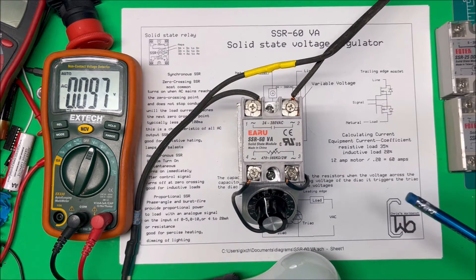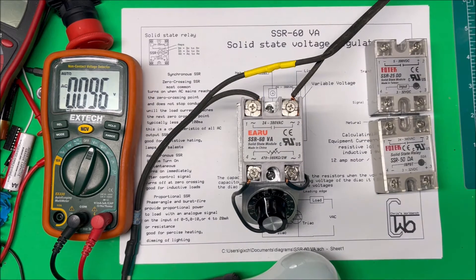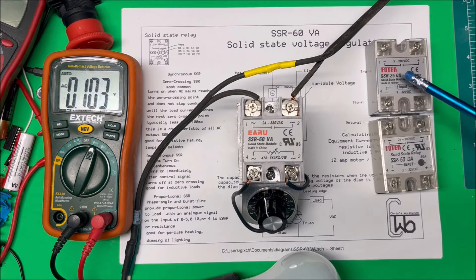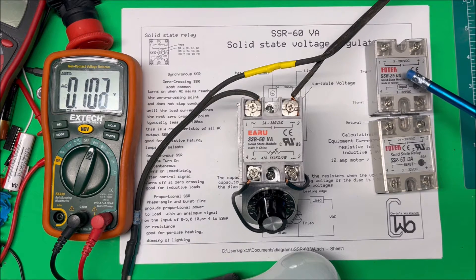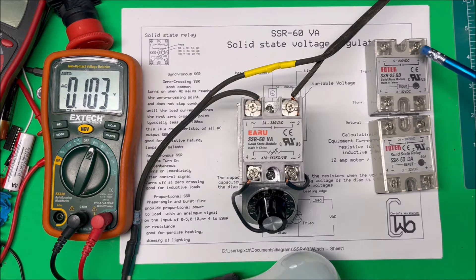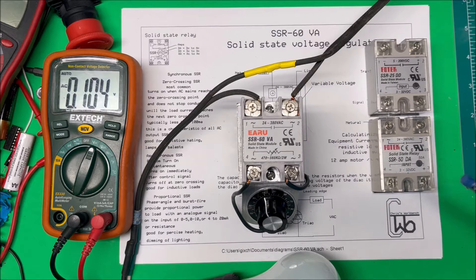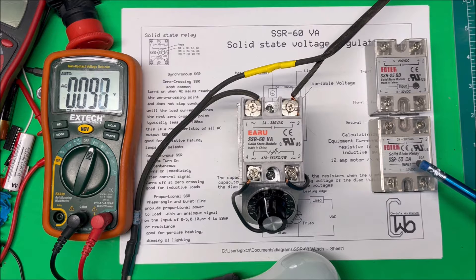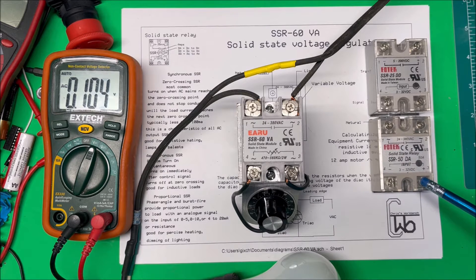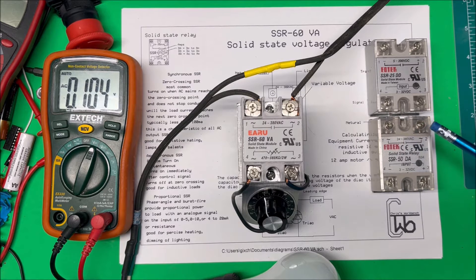These are the same form factor as solid-state relays. I've got a couple here. This one is an SSR-25DD, so 25 amps with a DC input and it switches a DC load. This one switches from 5 to 200 volts DC. And this one here is an SSR-50, 50 amps DA, so we turn it on with a DC input and it switches an AC load from 24 to 380 volts AC.